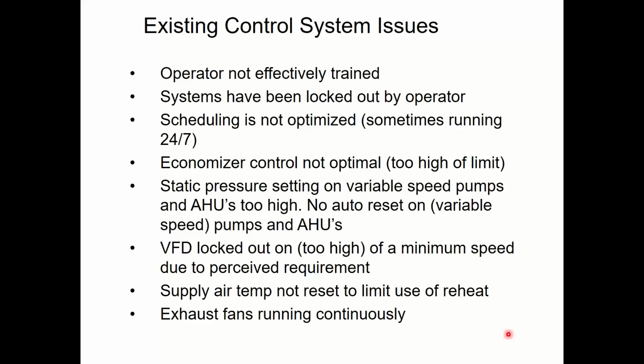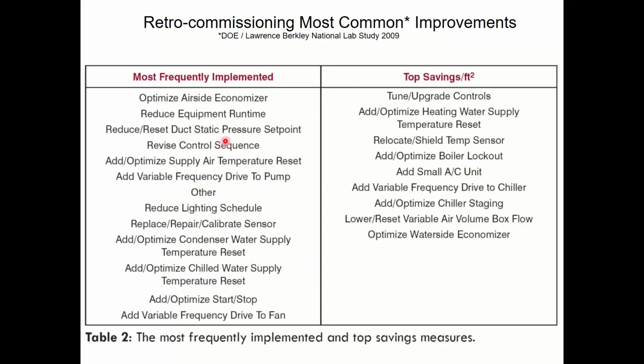The lack of reset controls on boilers, supply temperature sensors, chillers, all that stuff. Those devices typically have that reset built in, and it's frequently disabled by the operators. And then there's a lot of exhaust fans that run 24/7. There's more exhaust fans running 24/7 than there was HVAC and air handlers running 24/7. And there's a lot of those. So there's a lot of easy things we can do from the control standpoint to fix it.